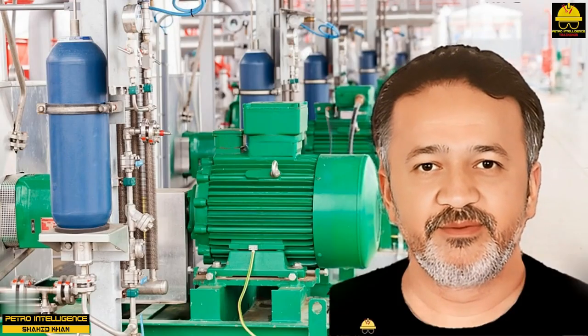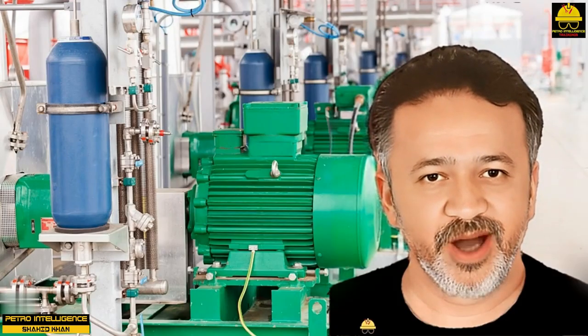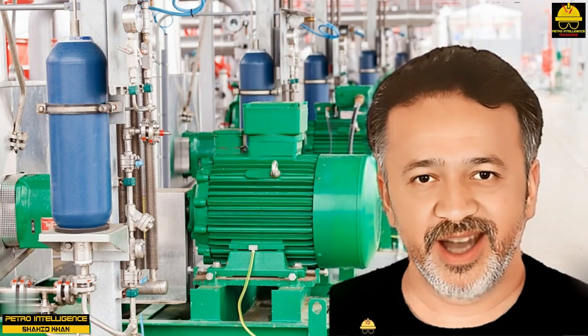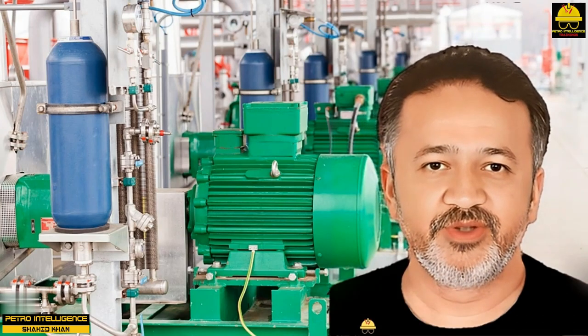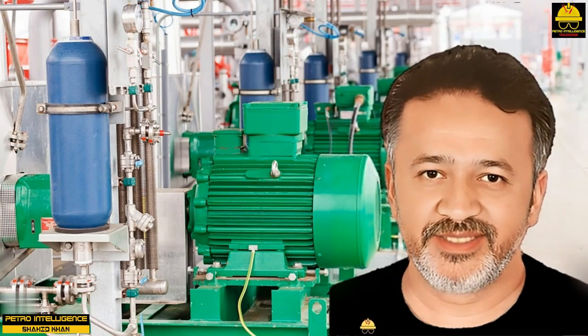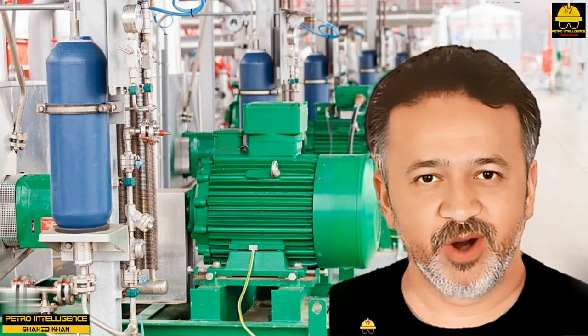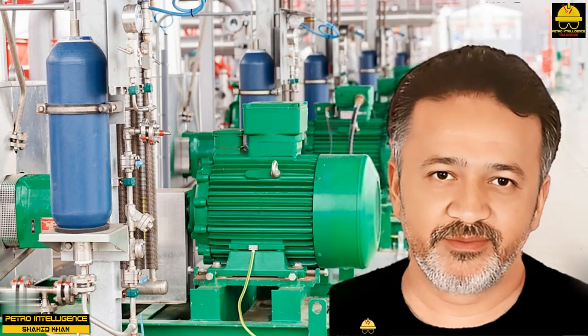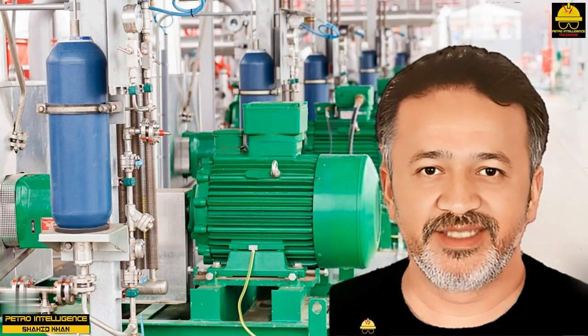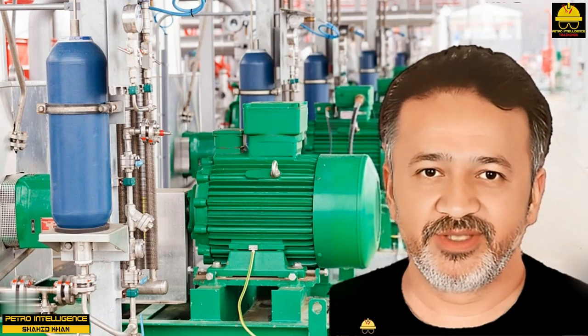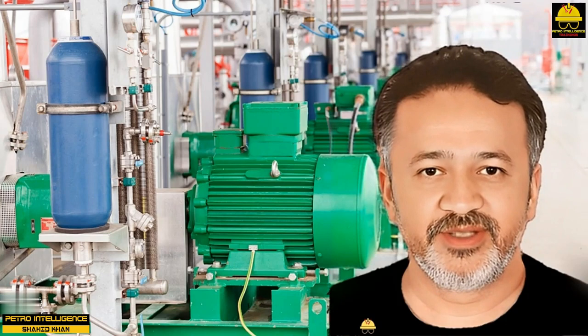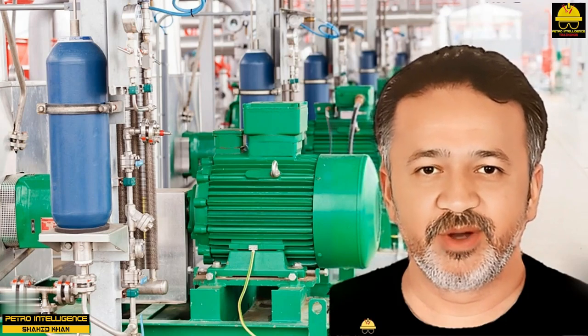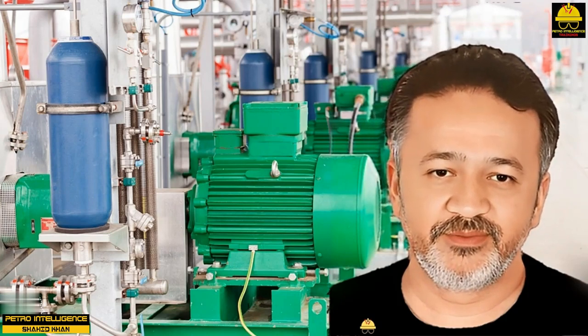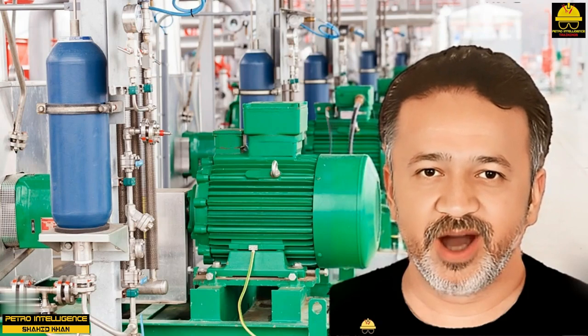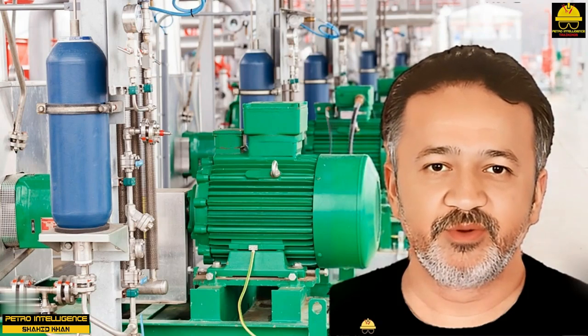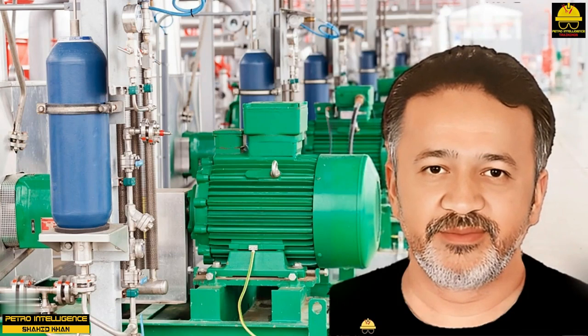Head pressure. In a centrifugal pump, fluids must be pushed, not sucked or pulled, into the impellers. Suction head is a term used to describe the pressure required to force liquid into a pump. Most processes are designed so that the suction pressure is sufficient to run the pump without cavitation, that is, the formation and collapse of gas pockets around the impellers. A centrifugal pump must be primed, full of liquid, before the pump can be started.